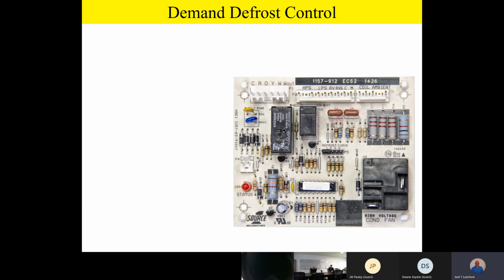And so that makes it a little bit more efficient, because if you think about it, anytime you go into the air conditioning mode in the middle of the wintertime and you bring on auxiliary heat, so you're air conditioning and you have auxiliary heat on, that's not a really efficient mode to be in. You're basically heating and cooling at the same time, and so that's not real efficient. So we try to reduce our defrost as much as possible on a heat pump. We want to make sure we defrost it enough to where it's going to stay efficient and the coil's going to stay clear and all that.